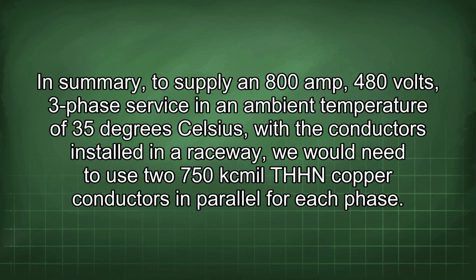In summary, to supply an 800 amp 480 volts 3-phase service in an ambient temperature of 35 degrees Celsius with the conductors installed in a raceway, we would need to use two 750 kcmil THHN copper conductors in parallel for each phase.